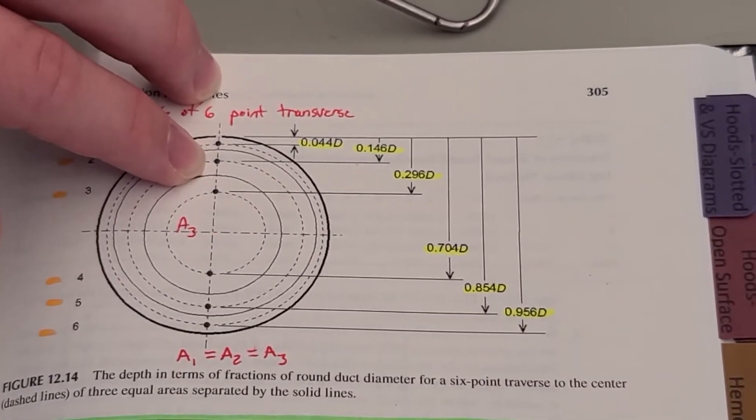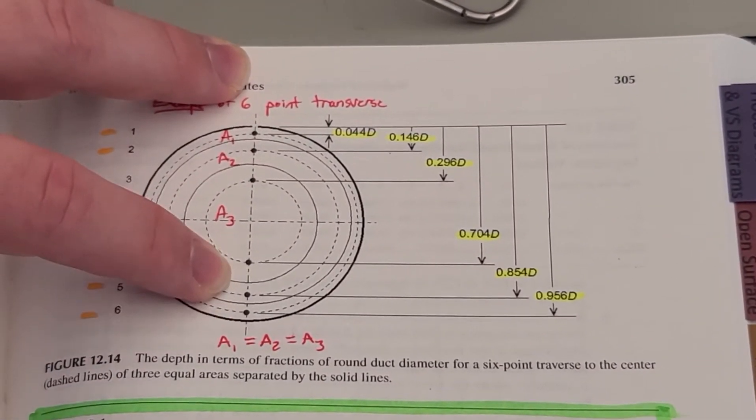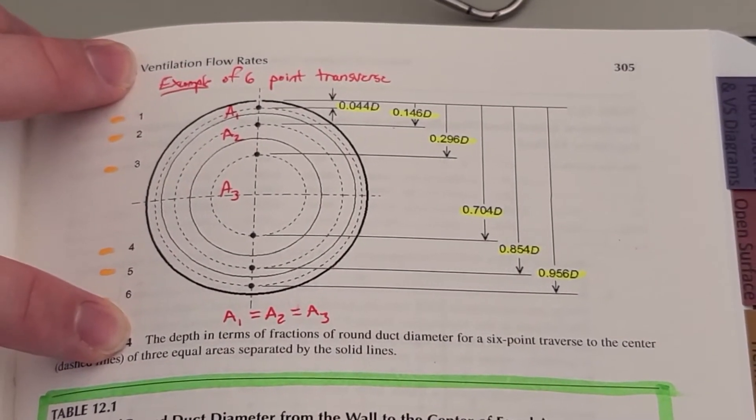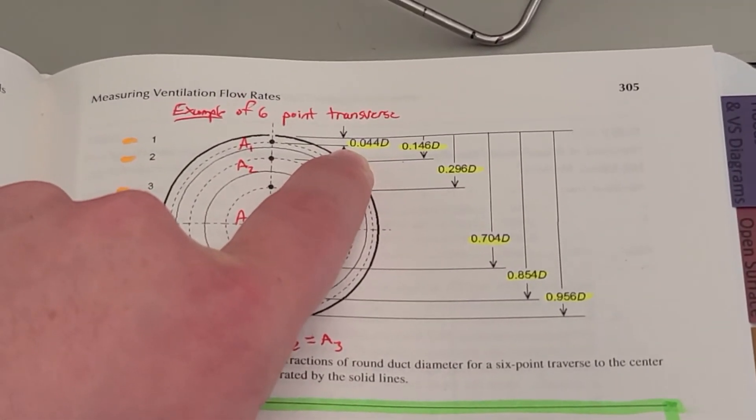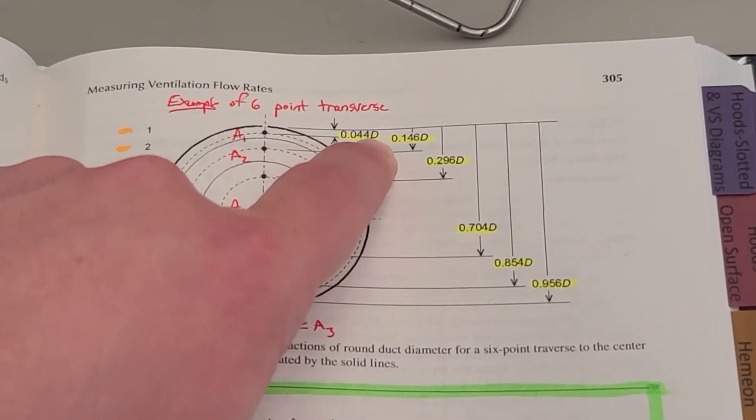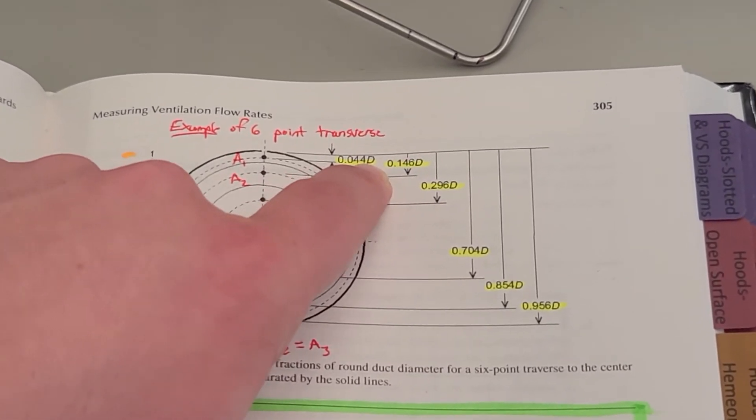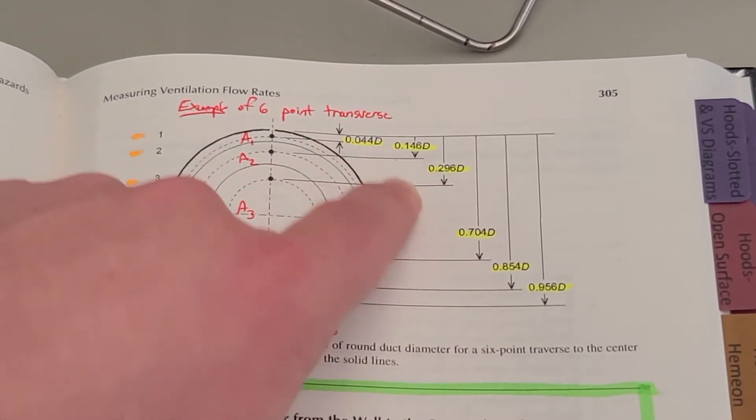The subsequent depths within the duct traverse are calculated based upon some fairly complex equations. It's much easier just to use a diagram such as this. Here we see that the first point within a duct traverse is 0.044 times the diameter of the duct. This diameter can be calculated in inches or feet, as long as you're using the same units throughout, whatever fits your duct best.